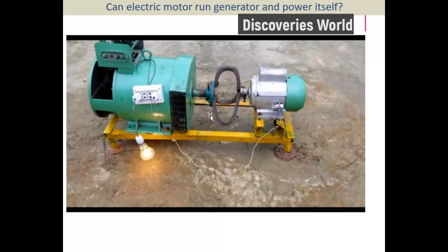Because you might say, okay, I have a 15 KVA generator and my motor is 1.5 KVA, but why is it not working? The fact that you have a 15 KVA generator does not mean that the generator is producing at 15 KVA. You must always use a meter to test it to know. Because if the generator is rated 15 KVA but the production ratio is not at 15 KVA — it might be at 12 or 7.5 or whatever — and the motor is drawing high current, there is no way it will power. That is why sometimes it goes down. You must understand this, and if you have this in your mind, you will always enjoy this system.